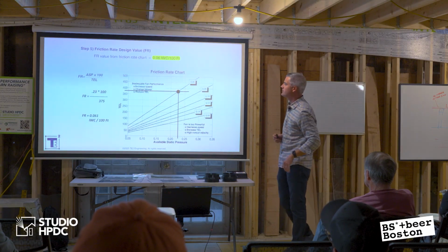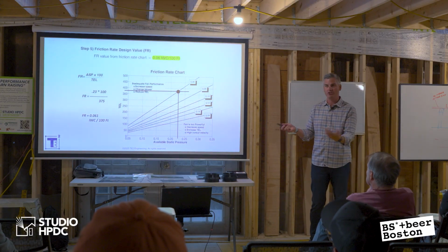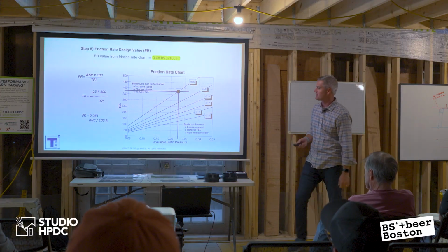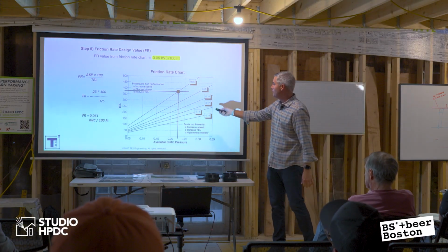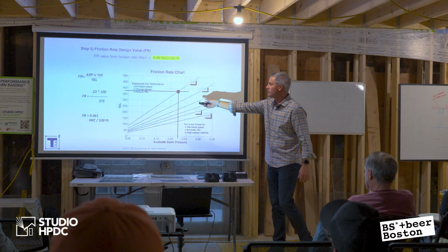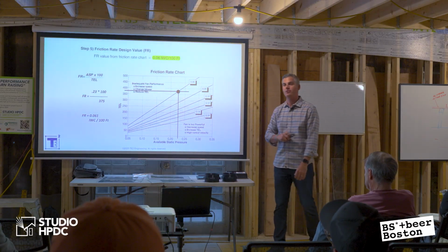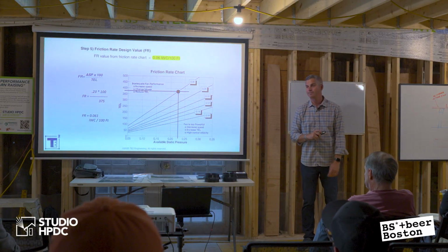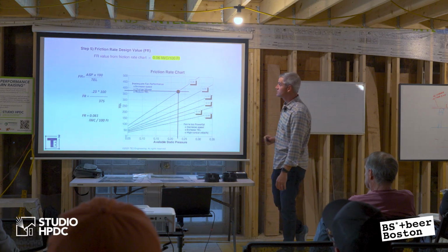So the resistance matters. Then you go to your friction rate chart, your ductulator. We call them fancy ductulator terms, one of my favorite words. And you basically look at your available static pressure and your total equivalent length, and you know what you need to design your ductwork for, so it's going to work right. That's your friction rate. Okay.